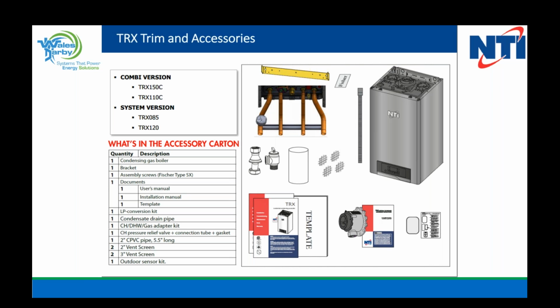Now, we go on a lot of these jobs with a lot of condensing boilers, not only the ones that we represent, because we'll be there to help the contractor on the system side of things. And a lot of times we see these boilers installed with a wire hanging out on the wall, and we know right away that was the outdoor sensor that somebody disconnected because they never set the boiler up properly so it can modulate properly. The homeowner was thinking, it doesn't feel the same because I'm used to having all this heat come on all at once. This is something, gentlemen, that we do have to educate our homeowners about, that this type of equipment is different. And we are matching BTUs, we're matching heat loss as needed.